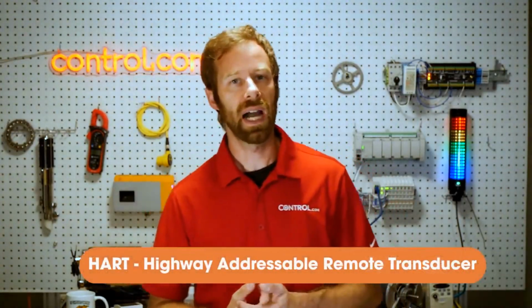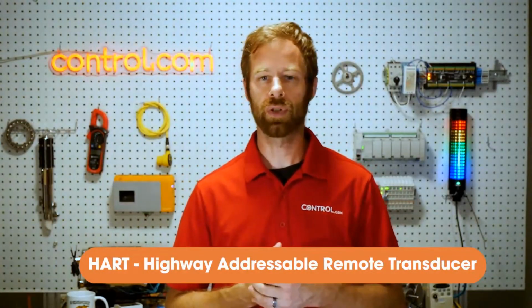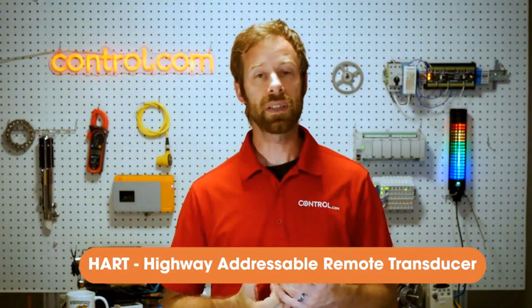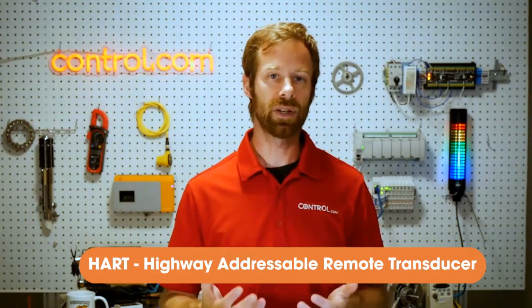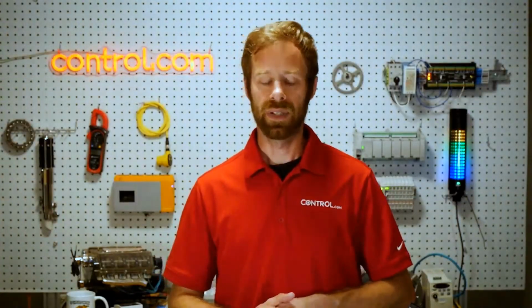Now, the next one of these device protocols that's connected directly to the devices is what's called HART, Highway Addressable Remote Transducer. And what this protocol is, it's a digital signal that's superimposed, or dropped right on top of, a 4 to 20 milliamp signal. Now, it doesn't happen with just a standard analog input. So you do have to have a HART input module or a HART communication module for your PLC.